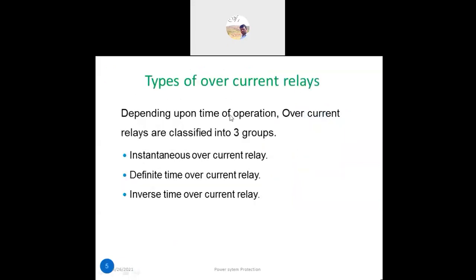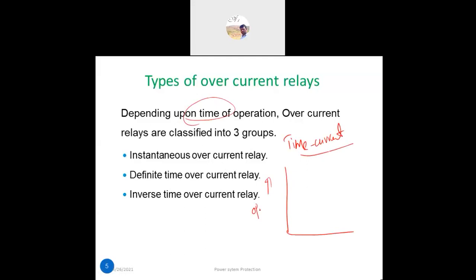Now let's look at the types of overcurrent relays. Depending upon the time of operation, overcurrent relays are classified into three groups: instantaneous overcurrent relay, definite time overcurrent relay, and inverse time overcurrent relay. We analyze these using time-current characteristics, with operating time on the y-axis and current on the x-axis.